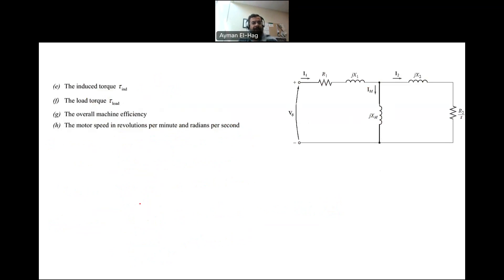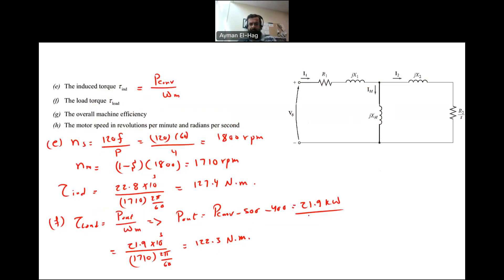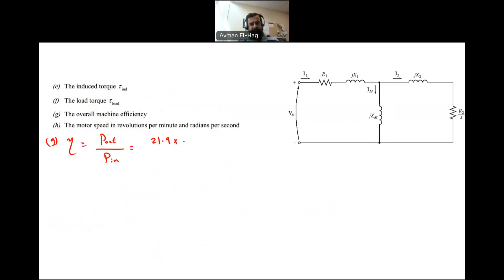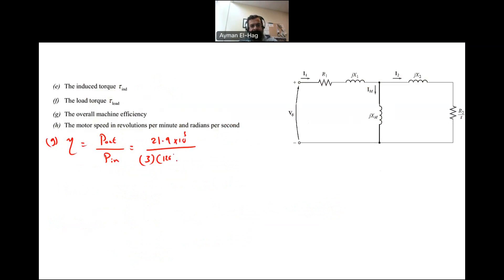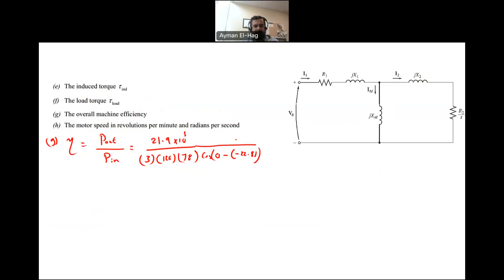For Part G, we find the overall efficiency: η = P_out / P_in × 100. P_out is 21.9 kW. P_in equals 3 × V_phase × I1 × cos(θ) = 3 × 120 × 78 × cos(0 − (−22.8°)). Calculating this, the overall efficiency of the motor is 84.6%.